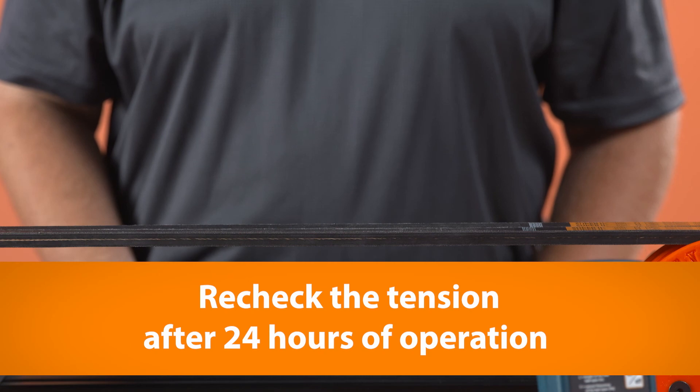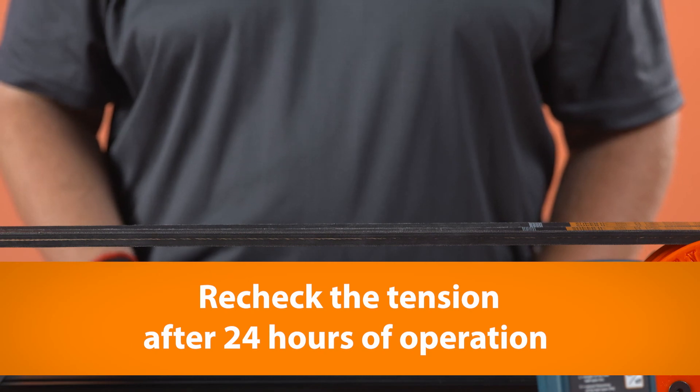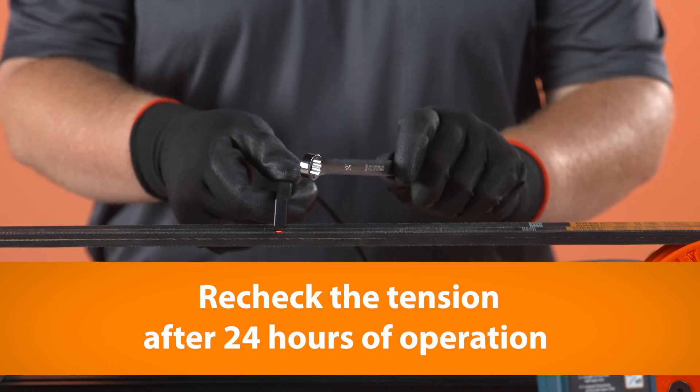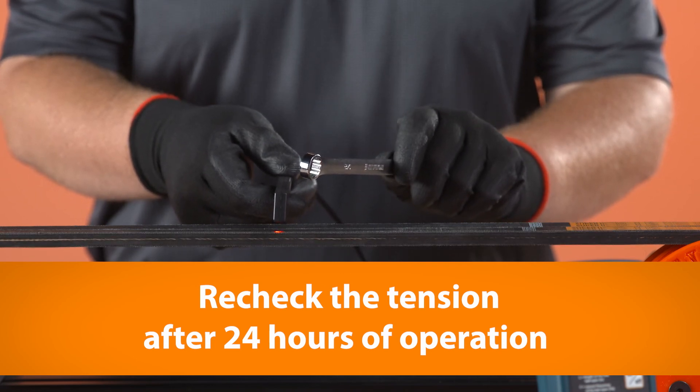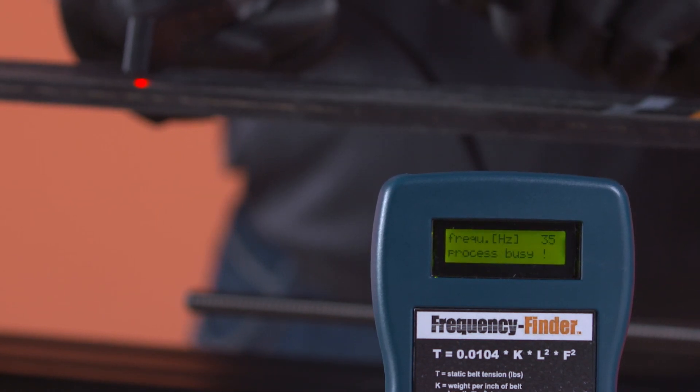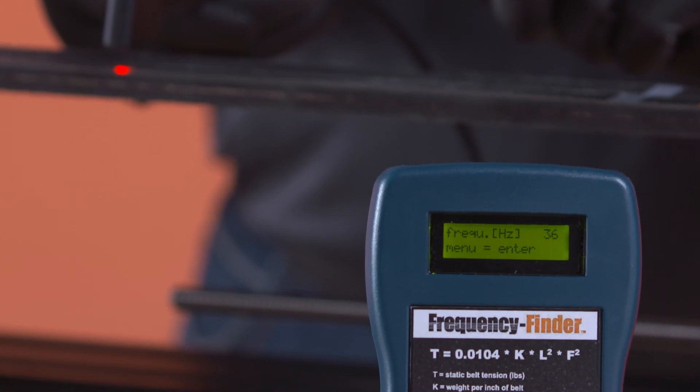One last tip. When installing new V-belts, check the tension on the drive after 24 hours of operation. Belts relax after seating fully into the sheaves. Checking them after 24 hours can often expose installation issues that were not obvious after they were first installed.